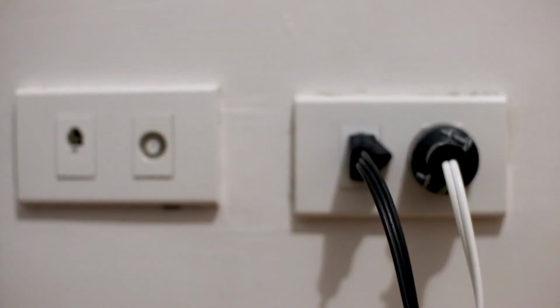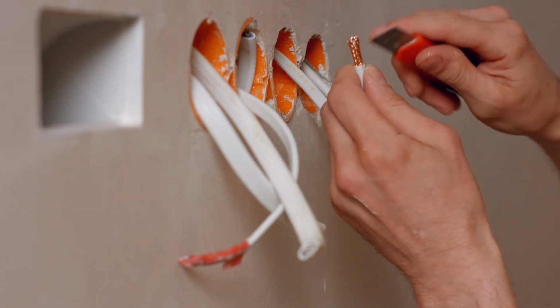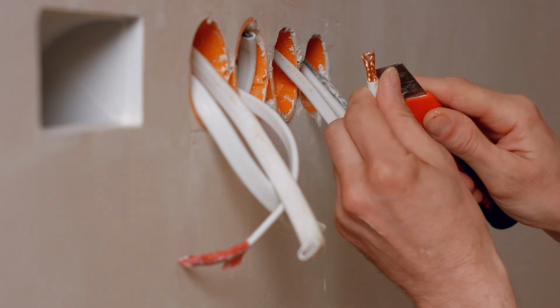It's our job to find out whether it's working or not. At the end of the day, if you have a plug point, it should work. Correct. That's very fair, and also in recent apartments, because of RERA, it's a mandate, so it takes that into account. Most of the time, it will be some loose connection. Exactly. Somebody has not put the wire properly in the connector. Very rarely are there wire defects; we've not found any till now. And you guys have done how many homes? We've done more than 4,500 individual clients.